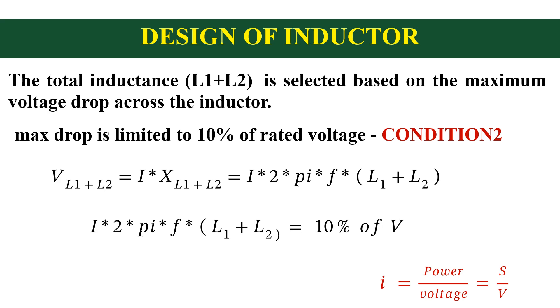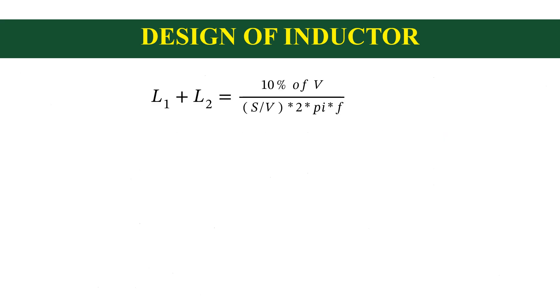Substitute in the equation, we will get L1 plus L2 is equal to 10% of V divided by S by V into 2 pi f. That will give L1 plus L2 is equal to 0.1 V square divided by S into 2 pi f.